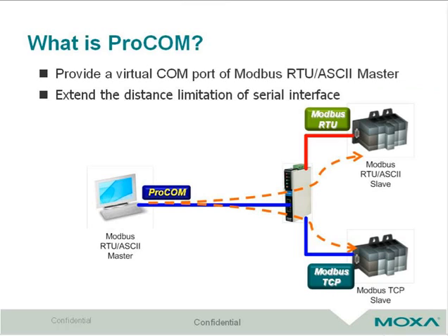ProCOM can provide a virtual COM port on Windows-based Modbus RTU masters to keep all the same settings as before. For example, through the SCADA software on the Modbus RTU master, it is still sending the port link through a COM port. Since this COM port is on the Ethernet, it can extend the distance limitation of the serial interface. It can connect to anywhere, everywhere.